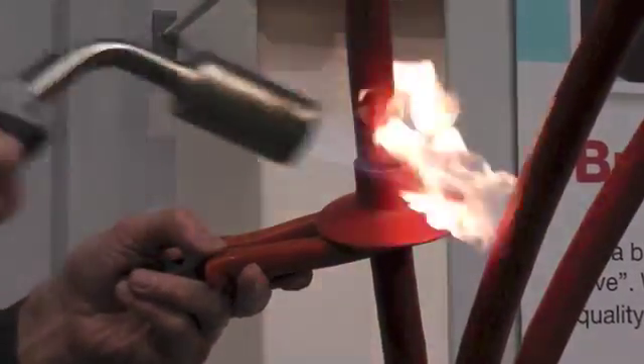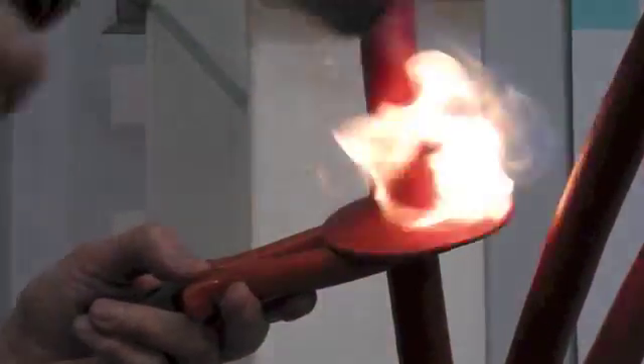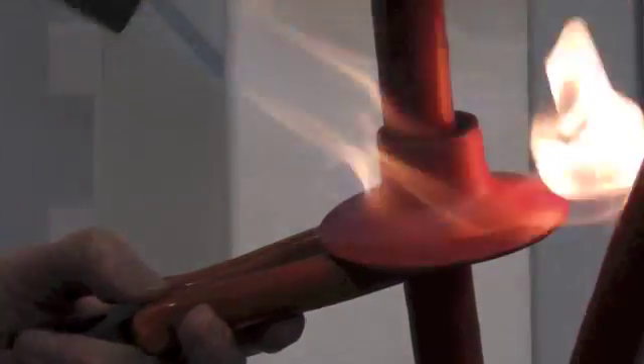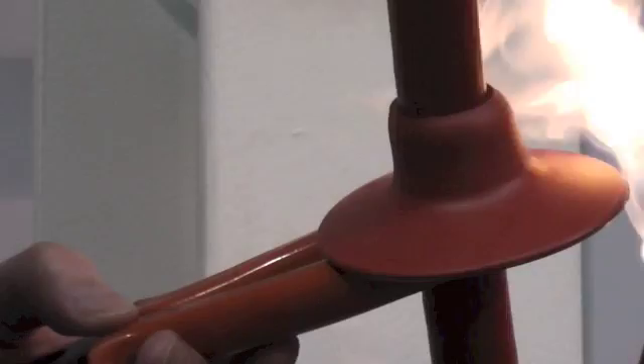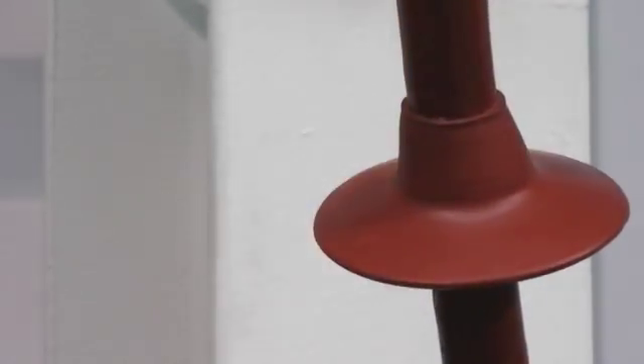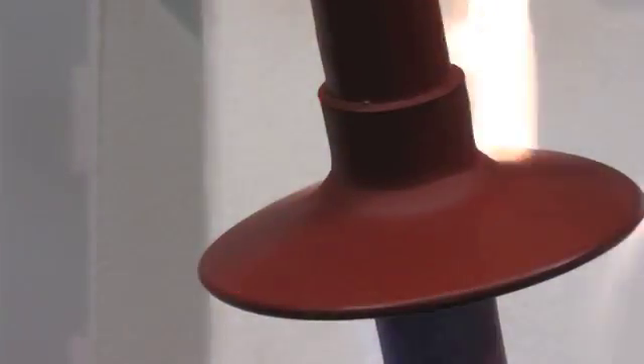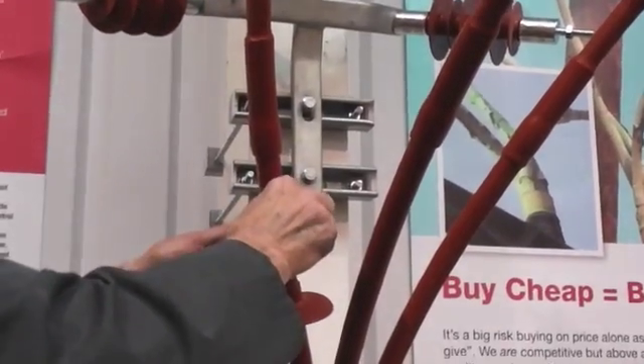Very often, outdoor terminations are completed on the ground and then winched up into a higher position. Sometimes the rain sheds can be easily dislodged during this process, and gaps can form behind the shed collar. If pollutants get in, they can cause tracking and eventual failure. So reheat the sheds if any signs of dislodgement have taken place.